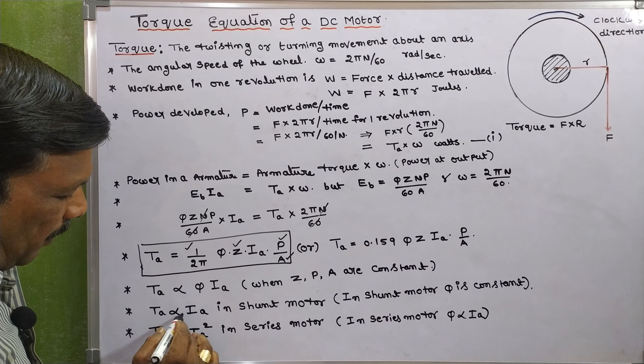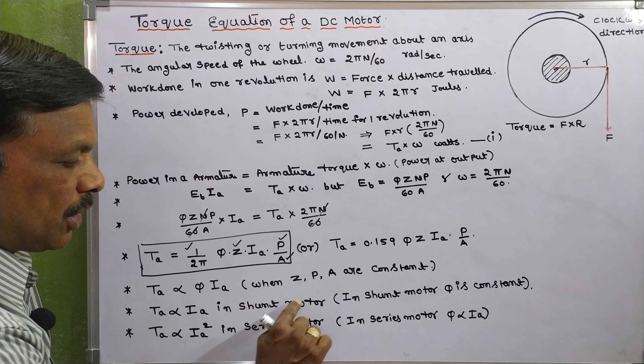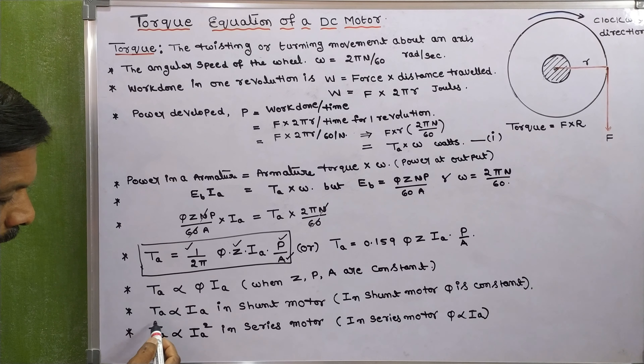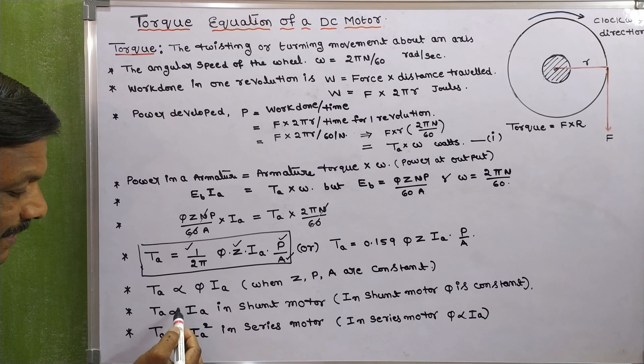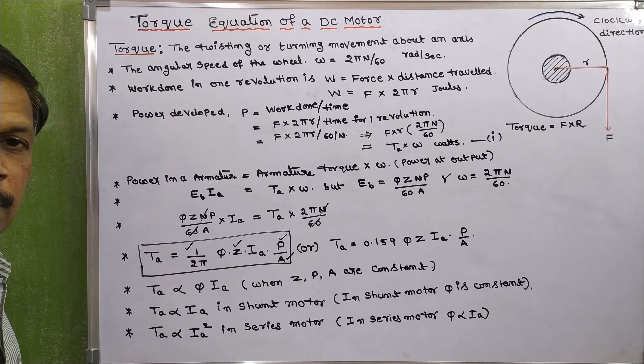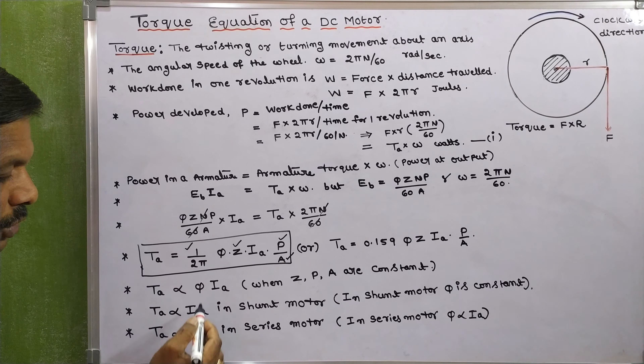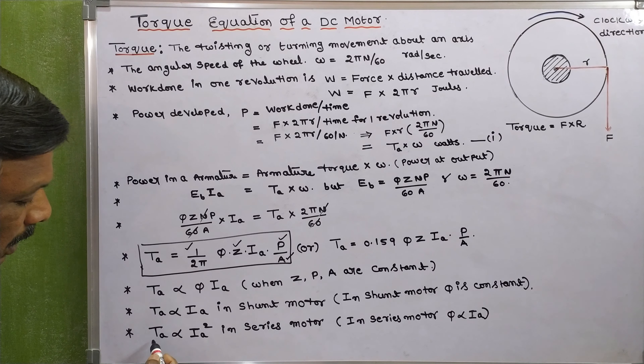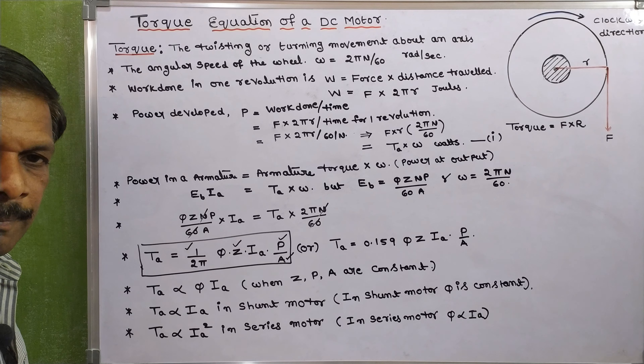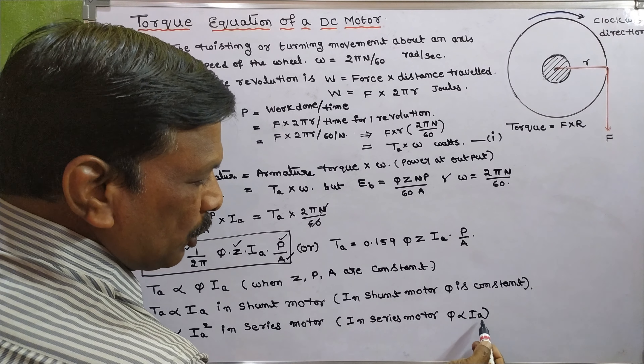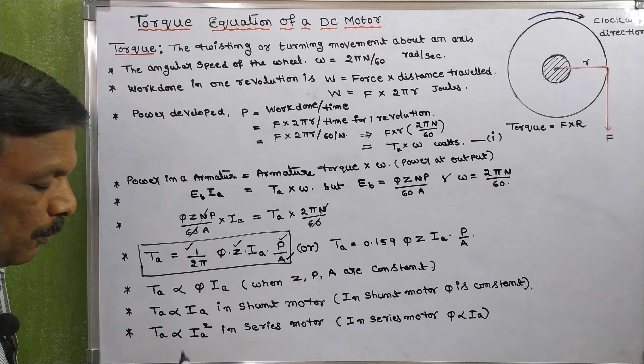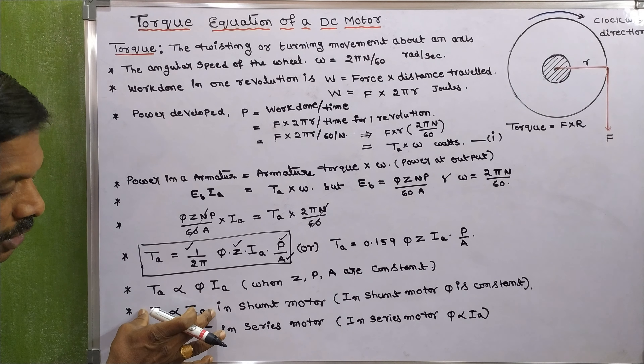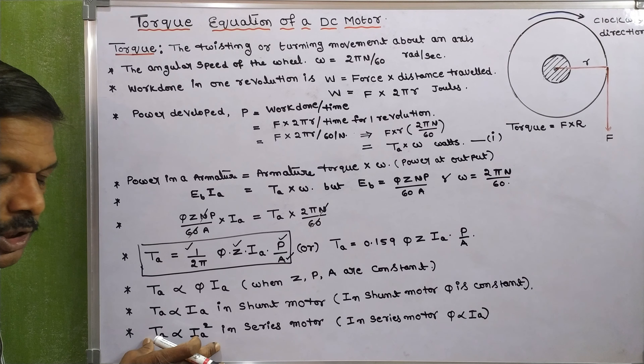Torque is proportional to I_A in a shunt motor. The general torque equation is T proportional to φ·I_A, but in a shunt motor φ is constant, so T_A is proportional to I_A. In a series motor, torque is proportional to I_A squared, because in a series motor φ is proportional to I_A, so torque is proportional to I_A × I_A = I_A².